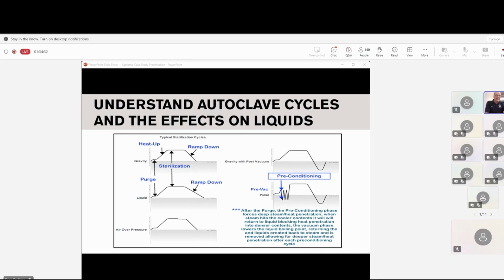I didn't do anything over the air, over pressure. That's for the bulk sterilizers. You won't see that in the smaller ones. It's a very specific cycle that it runs because of the bulks. And for those that have never seen a bulk sterilizer, you can park cars and trucks and everything else in them. They're absolutely massive, and I've worked on them all over the country as well. Gravity with post-vacuum, we don't fool with those either. If you can pull the vacuum, you better have a pre-vac cycle on there. So we're going to go to the big 3.